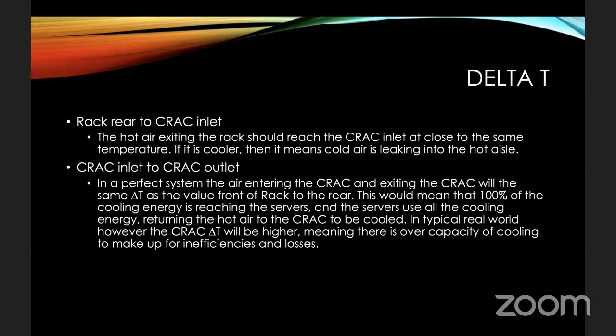So the hot air exiting the rack should reach the CRAC inlet at close to the same temperature. So if I have 35-degree air coming out of my rack and I have 35-degree air going into my CRAC, that means everything is working 100% efficiently. That air has not lost any of its heat. Now, how would it lose its heat? If it's 35 coming out and it's 30 when it reaches the CRAC inlet, does that mean that I have cold air leaking from my cold aisle to the hot aisle? Because somehow that air coming out of my rack has been cooled down before it reached the CRAC. If that's the case, then possibly I have something going on.